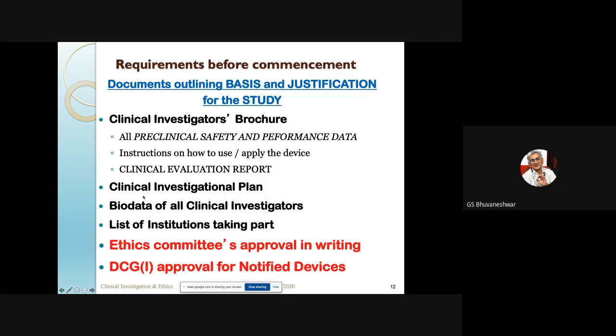As I mentioned, just to repeat, the clinical evaluation report is a review of your predicates, of the treatment that is given, and all the risks involved, and includes a risk analysis of all your data and shows how you have controlled the risks. Generally, you'll also need a risk analysis report or a risk control report as part of your brochure.